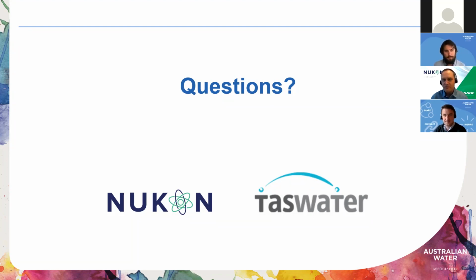As a solution for analytics, Seeq is very good value for money. If you've got a very small system with a small number of users, it is a good solution that will scale down to small systems. You may have to select a slightly different back-end solution for storage of the data, or perhaps you already have one, maybe a small scale historian type solution just to collect the data from the field. I mentioned earlier that we're not collecting a lot of data from the field - we actually only collect the run signal for each pump to generate this analytics. So it's really just one bit per pump from the field, and that's fairly typical telemetry that would already be coming in from those systems.